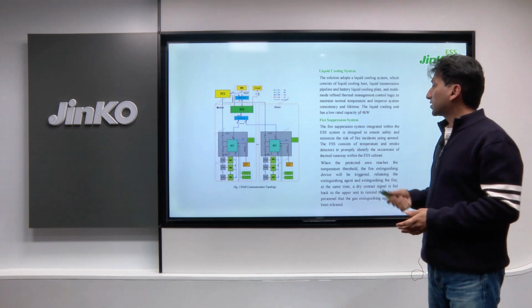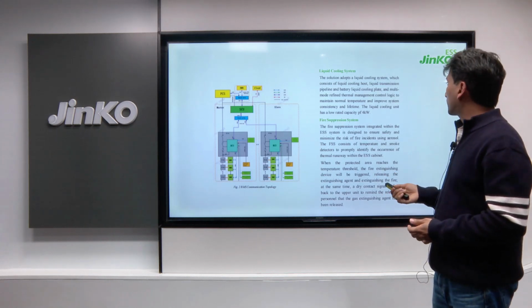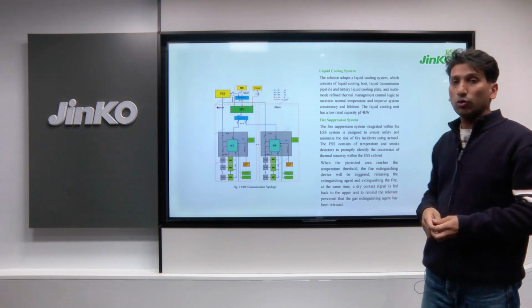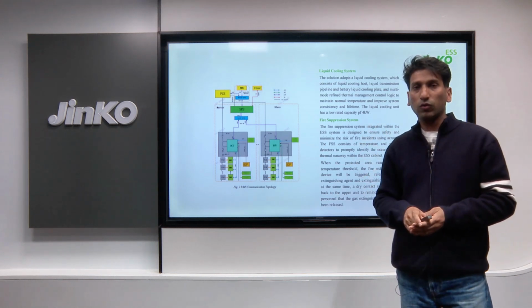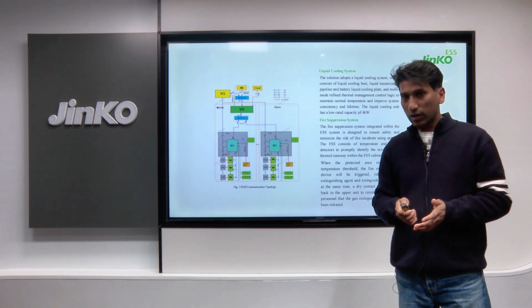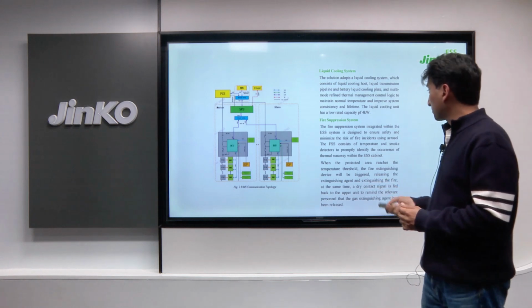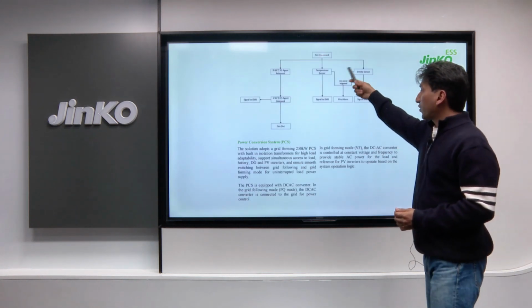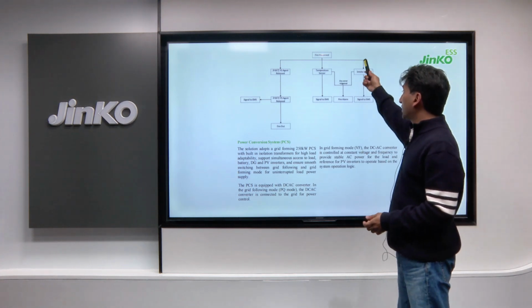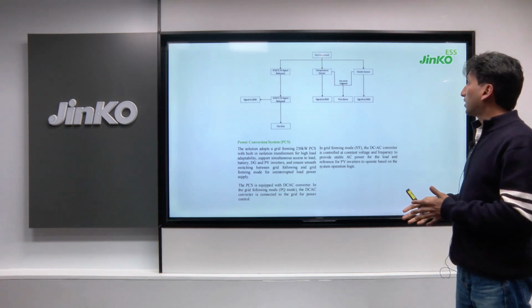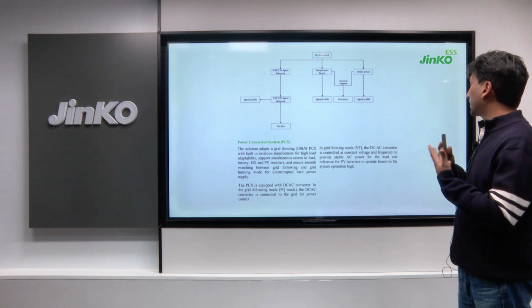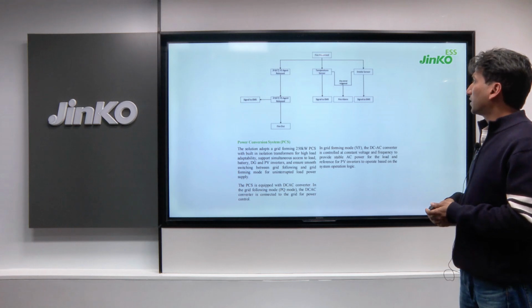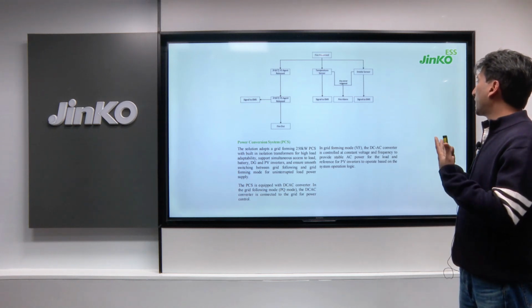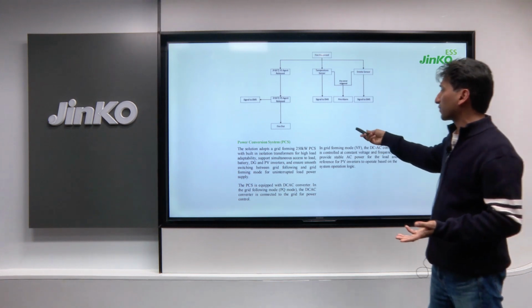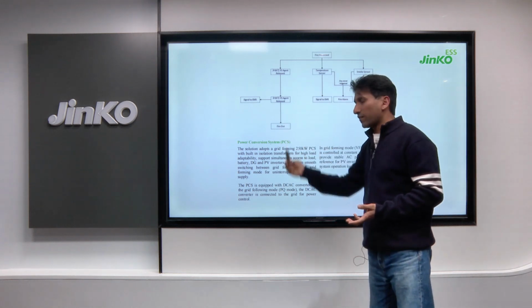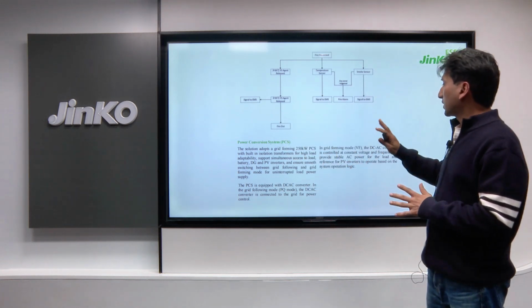This liquid cooling system also has a fire suppression system. The whole cabinet has fire suppression, so in case any fire happens, it can be extinguished inside the cabinet. This diagram is about our fire system. If fire happens, we have temperature sensors and smoke sensors. If they sense a fire, the fire alarm will start, and it will send a signal to the fire system, which will start working and extinguish the whole fire.